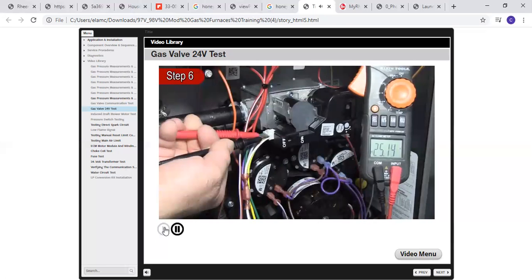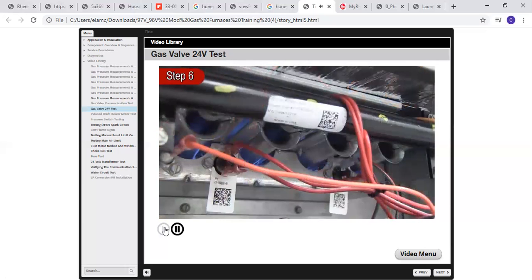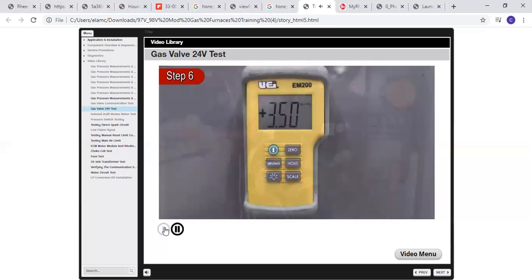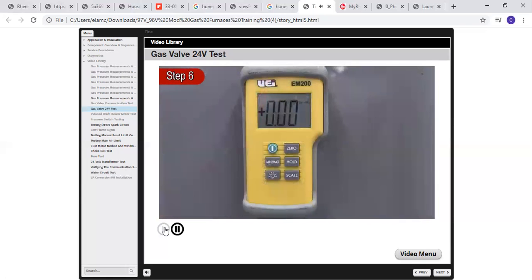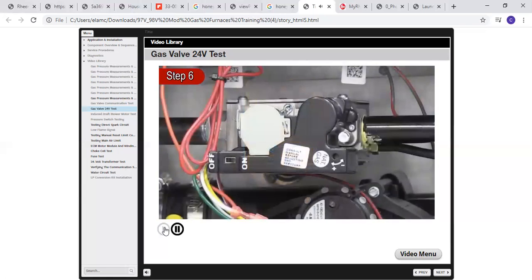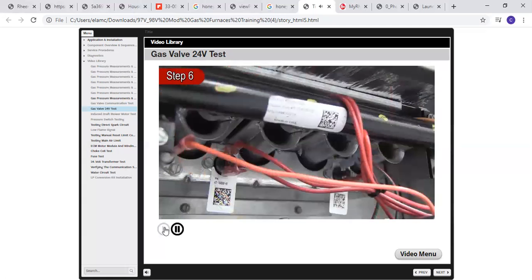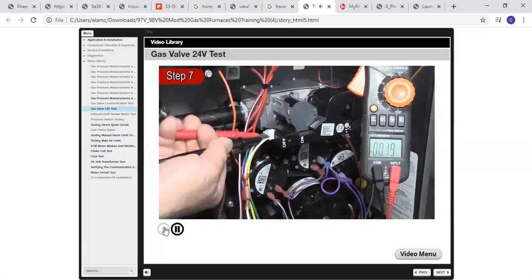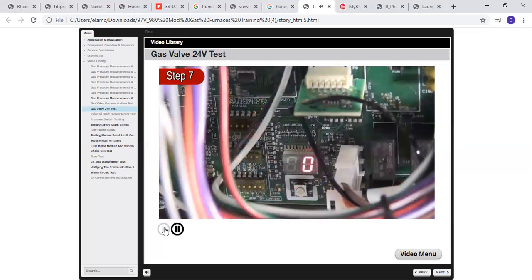Step 6. If voltage is present, the valve should open to allow gas to flow to the burner. Check for outlet pressure. If the voltage is present, but there is no gas outlet pressure, replace the gas valve. If there is outlet pressure, the burners should light. If the burners do not light, perform a direct spark igniter test. Step 7. If voltage is not present at the gas valve, allow the furnace to go into a retry cycle.